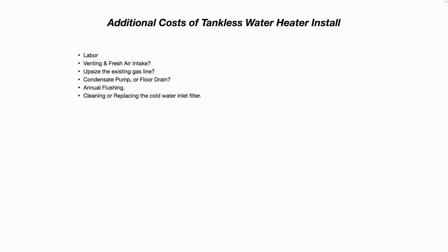And then annual flushing. Tank type water heaters, you can get away with not flushing them. Some plumbers do highly recommend flushing tank type water heaters, but tankless water heaters, you can't not flush them. If you don't flush your tankless water heaters, the minerals and calcium and sediment will build up inside, particularly in the heat exchanger, and it'll reduce the efficiency of the unit. It'll cause error codes, and if it's bad enough, it can actually cause a unit to shut down where you have no water flow coming out of the tankless, or you'll have no hot water, or you'll run out of hot water, or low water pressure.